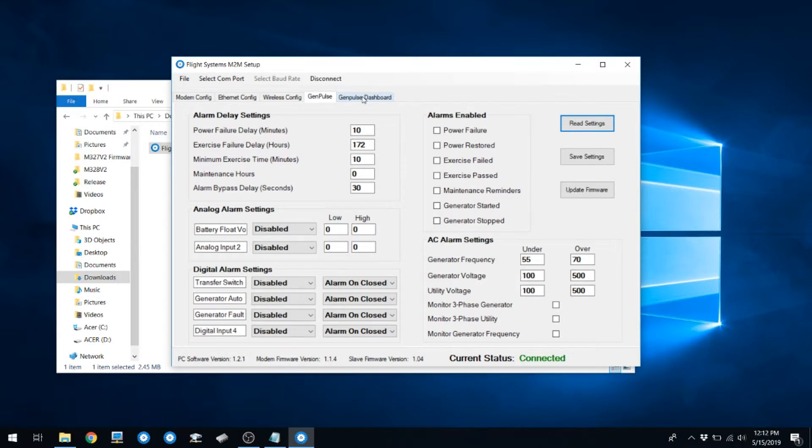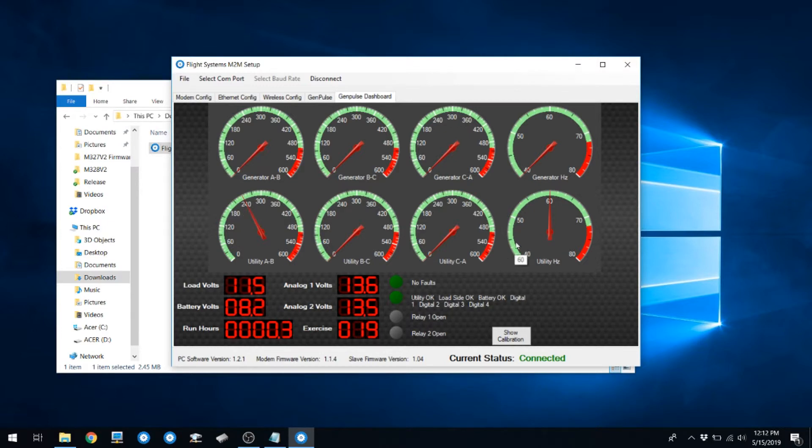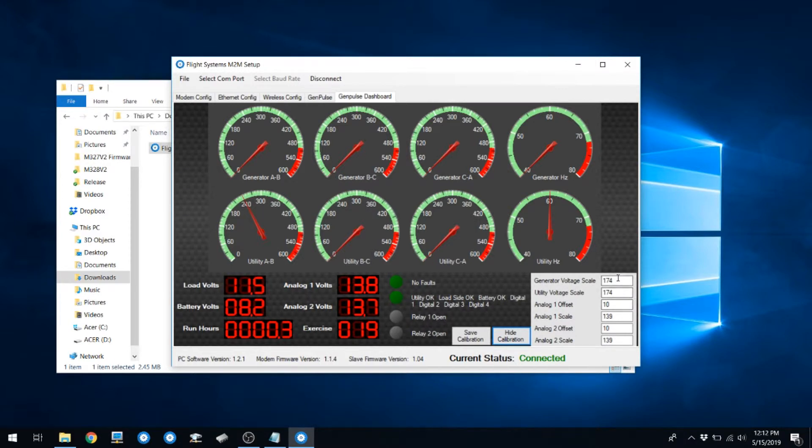You can also click on the GenPulse dashboard page and ensure you have utility voltage and frequency. You can also click on Show Calibration and adjust your scales to dial in the readings that are displayed for utility and generator voltage.